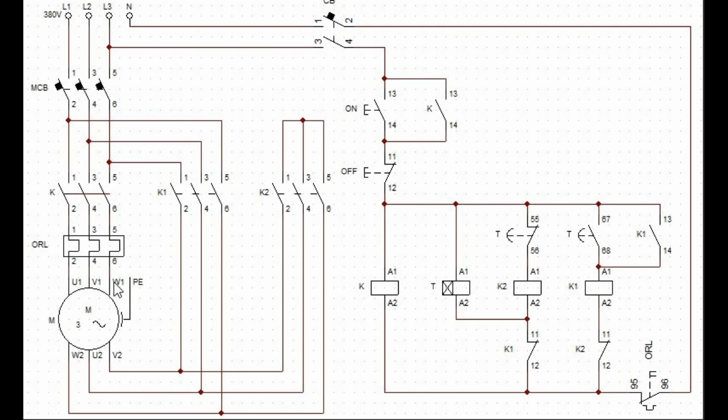Now let's move to contactor K1. Three phases from the MCB are connected at the input of contactor K1. The output of K1 contactor is linked with contactor K2 and also connected to the motor terminals, respectively L1 connected to V2, L2 connected to U2, and L3 connected to W2.